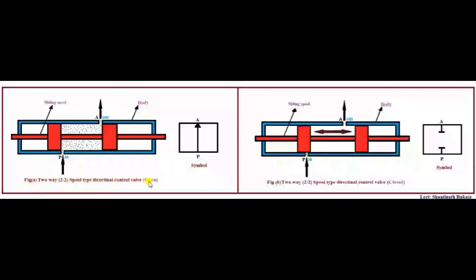Figure A shows case 1, that is the valve is in open position, and figure B shows the valve in closed position. In case 1, when the sliding horizontal spool is at rest, the fluid enters the inlet port and directly flows out through port A as shown in the figure. In the symbol, the fluid enters at port P and directly flows out through port A.